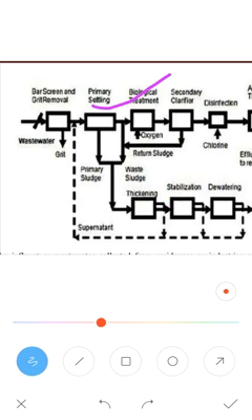So later, the effluent which comes out of this primary settling tank is subjected to biological treatment, or secondary treatment. Here the decomposition of organic material takes place in the presence of oxygen, by aerobic bacteria, with the supply of oxygen. Then the stabilized organic particles, along with the water, pass through the secondary clarifier, where the stabilized organic matter settles at the bottom of the tank.